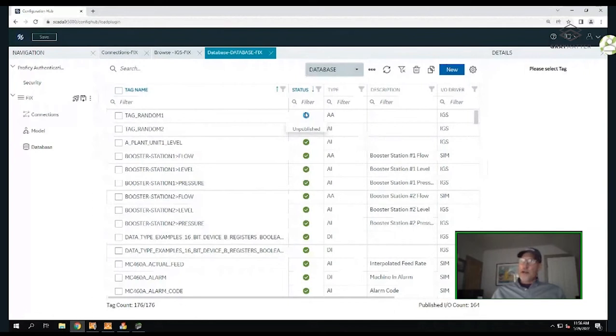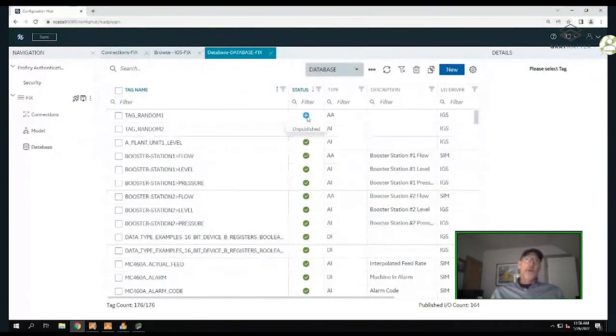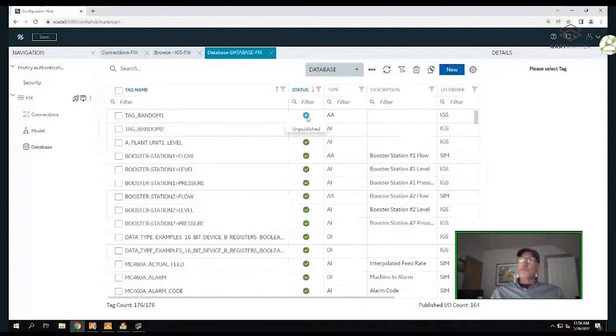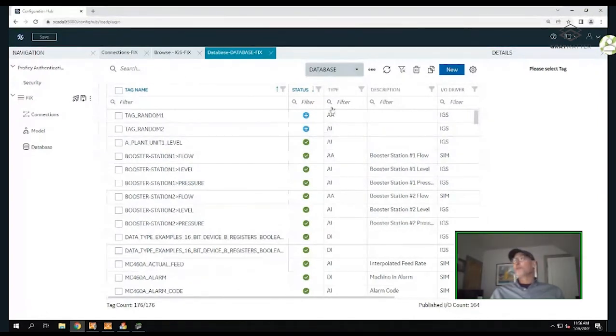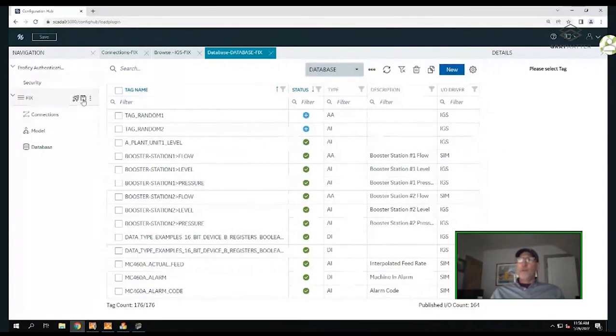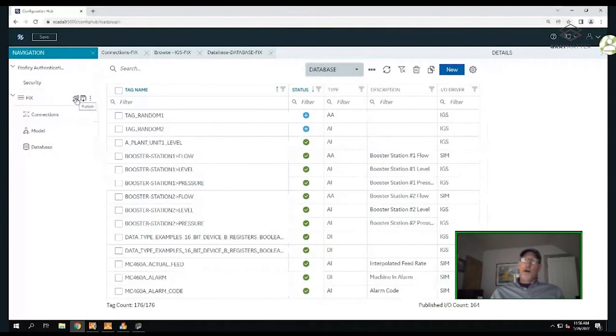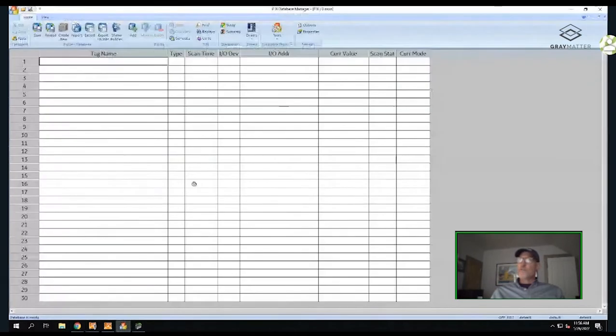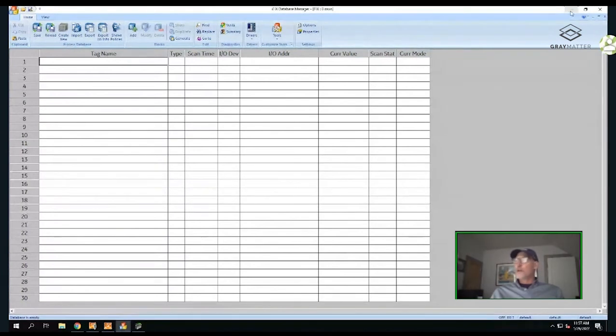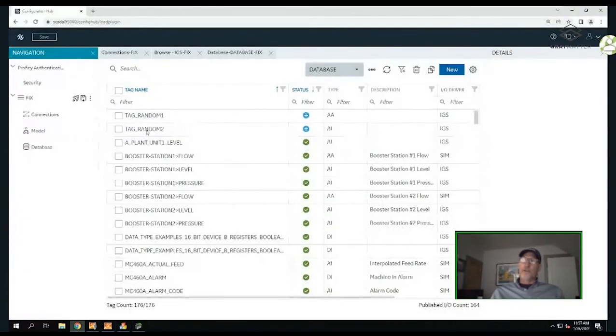Notice a couple of new icons - unpublished, and the ones that are checked are called published. This allows me to build the iFIX database really offline, something we didn't really do in the past. I can build this configuration offline, and when I'm done, I can publish it. You can save your selection, and you can use this icon to publish your tags. The traditional database manager still works, but in addition we now have this Configuration Hub environment.